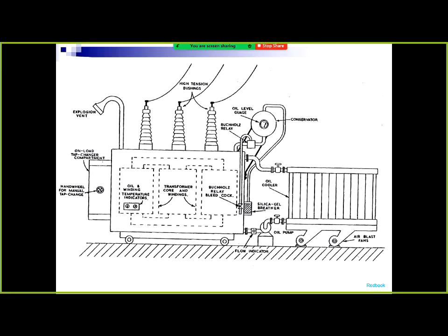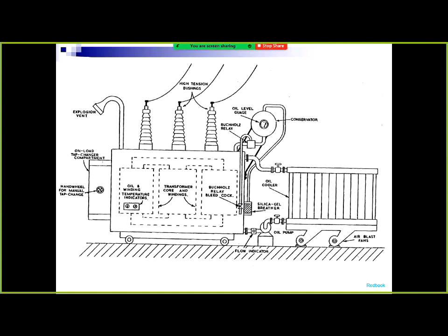Up on the top right there, or not quite top right, you'll see the Buchholz relay and an oil temperature gauge and oil level gauge, to see your level there. And that's in the conservator up on the top there. And inside the transformer there are also oil and winding temperatures, OTI and WTI, as they get abbreviated.